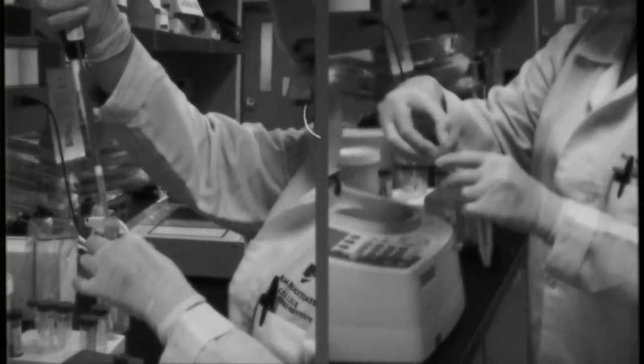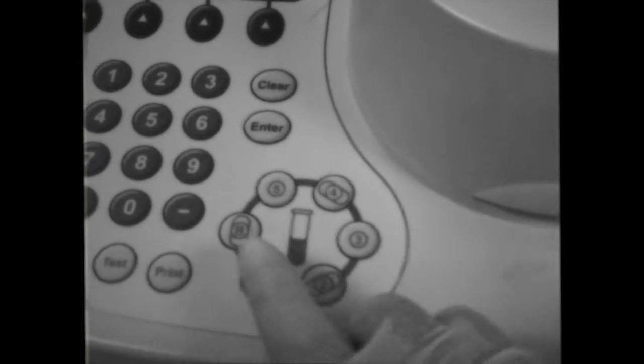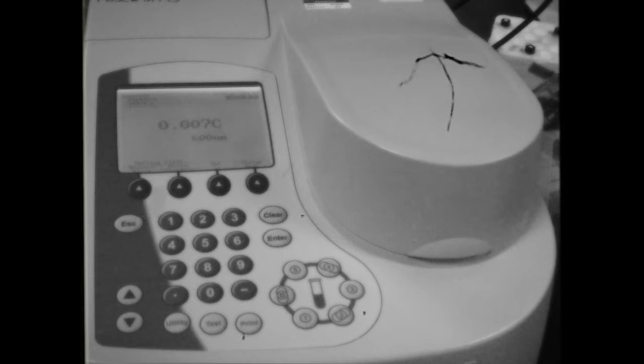Another cuvette is loaded with a pure version of the sample to provide a baseline. The scientist measures the blank, or pure sample, first to get straight zeros on the readout, then presses the 1 key to move the sample in front of the light to find out the concentration normalized to the pure solution.